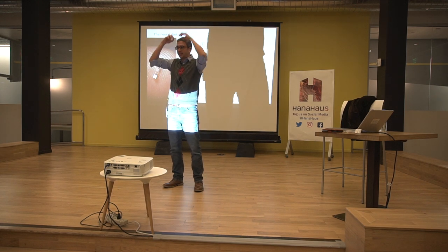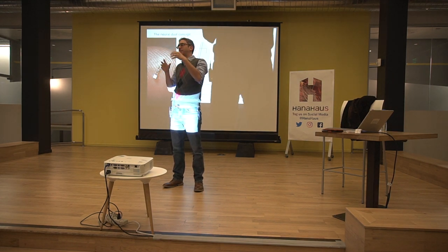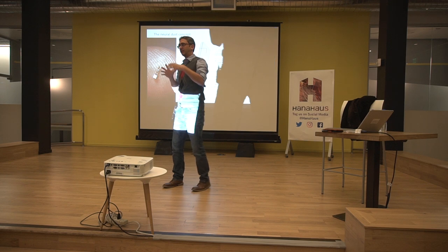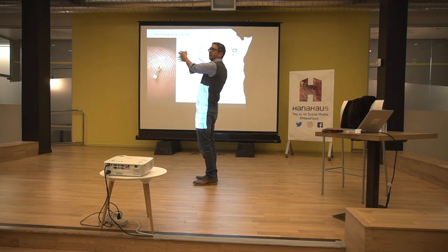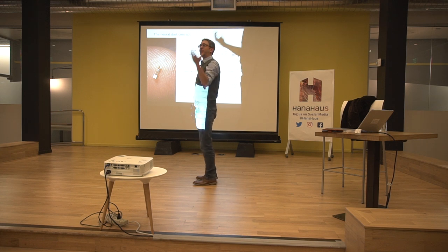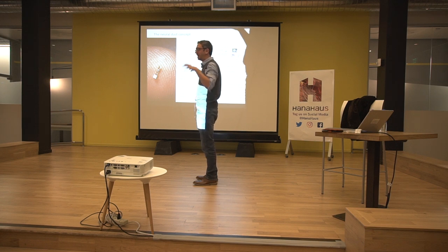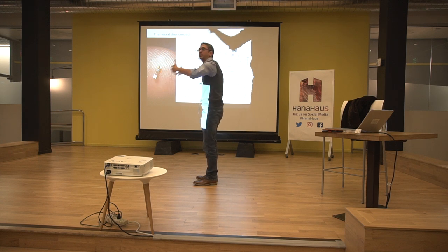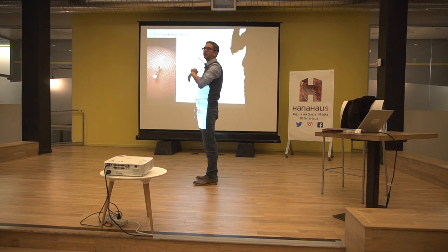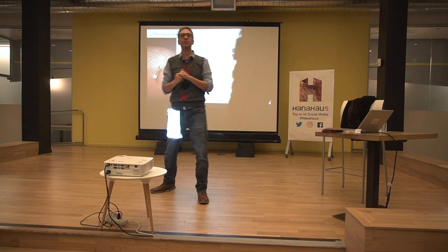One is, let's say I have a couple of implants or many implants all sitting near each other such that I can just take my system and talk to this one and then steer the beam and talk to the next one, and I could raster. I could do that. Another thing I can do, which I'm going to show you, this is actually you're perfectly preloading a whole part of my talk. I can just wash all of them with ultrasound, with one plane wave ultrasound, have many, many receivers. And as the reflections come back, I can use machine learning to figure out who's changing where and build a library and listen to all of them all at the same time. And I'll show you that. So I'm kind of jumping ahead.